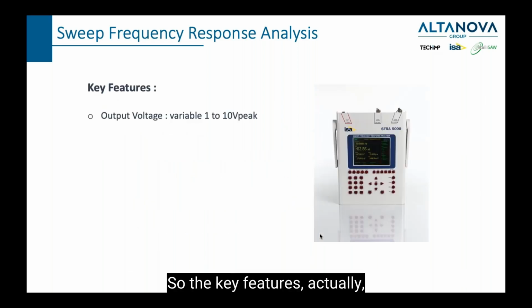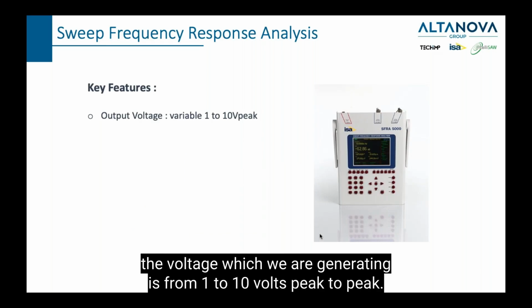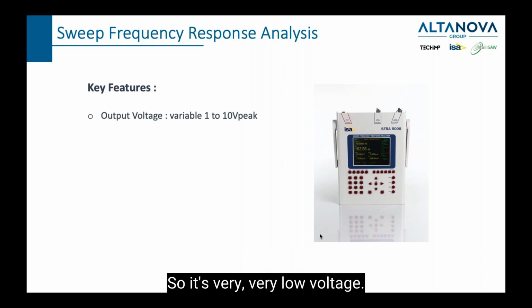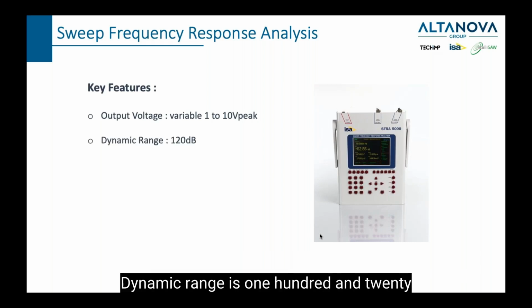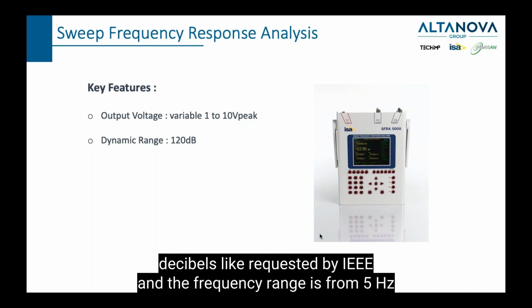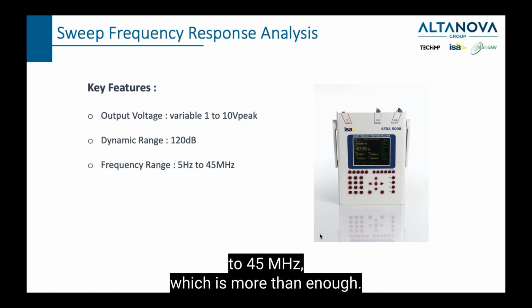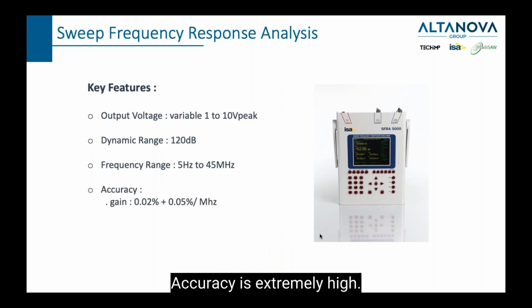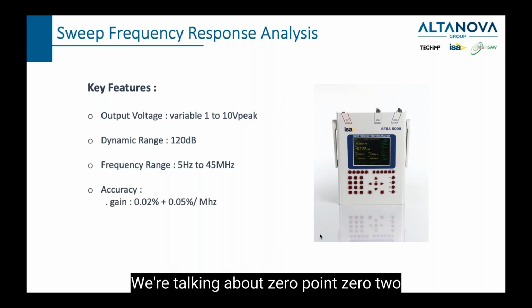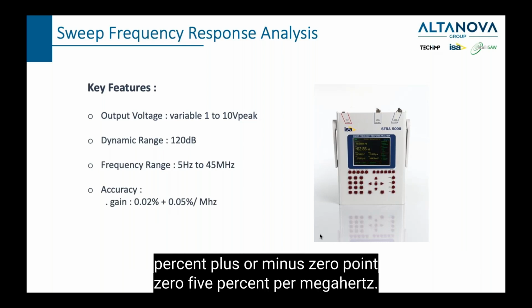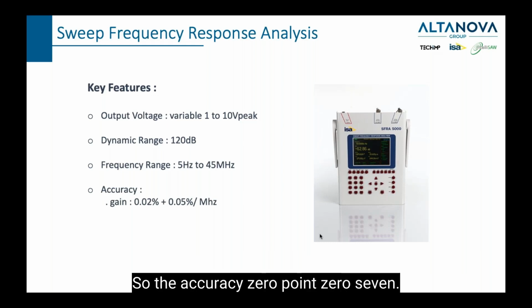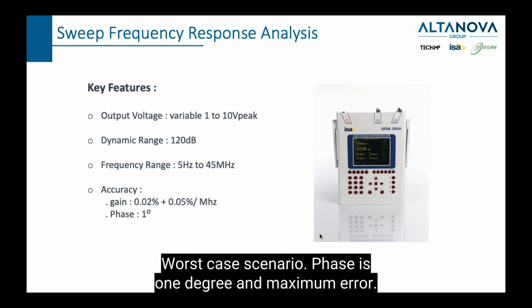a delta. So the key features, actually the voltage which we are generating is from 1 to 10 volts peak to peak. So it's very, very low voltage. Dynamic range is 120 decibels, like requested by IEEE, and the frequency range is from 5 Hz to 45 megahertz, which is more than enough. Accuracy is extremely high. We're talking about 0.02% plus or minus 0.05% per megahertz. So the accuracy is 0.07 worst case scenario.